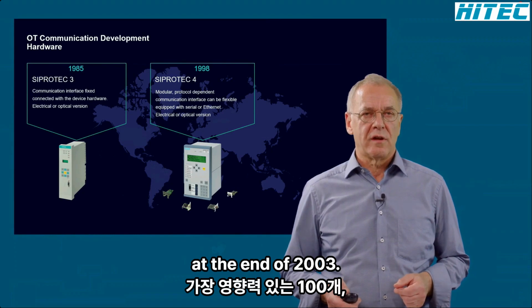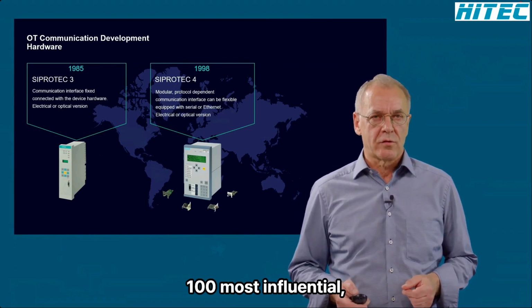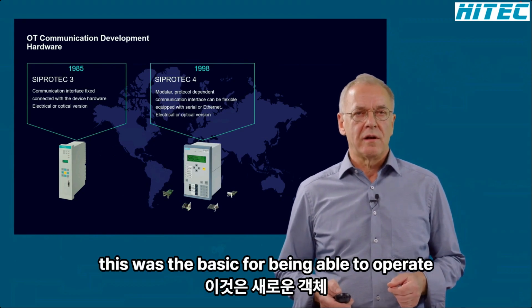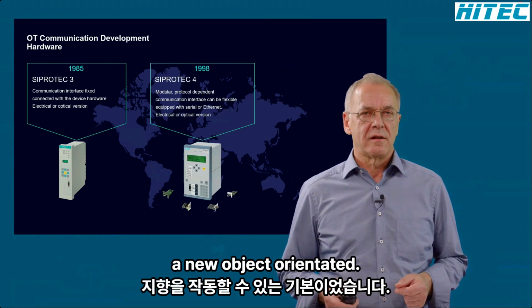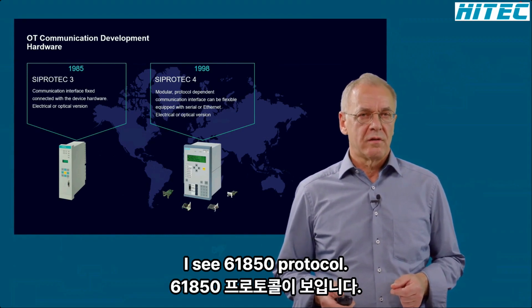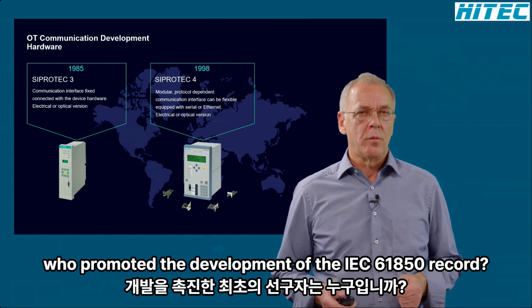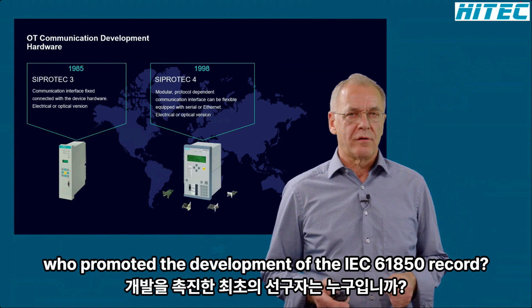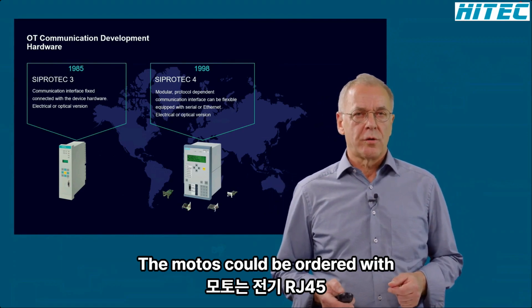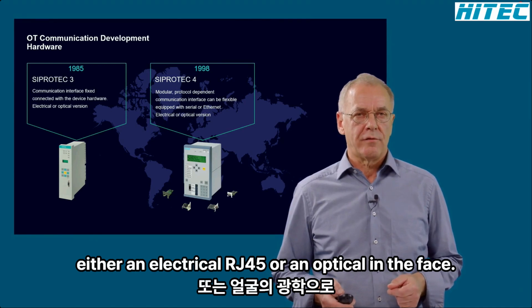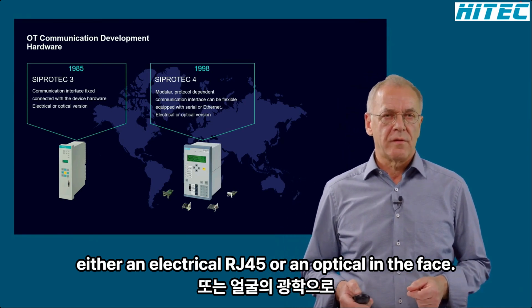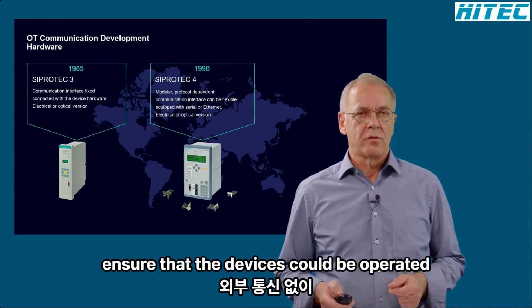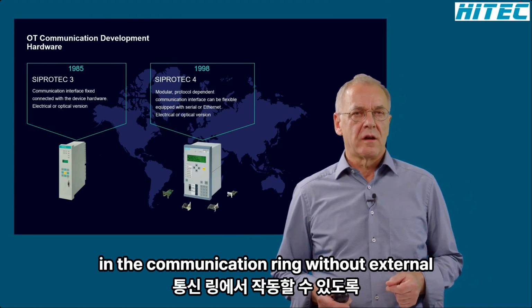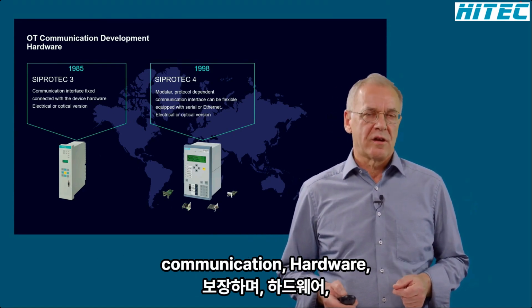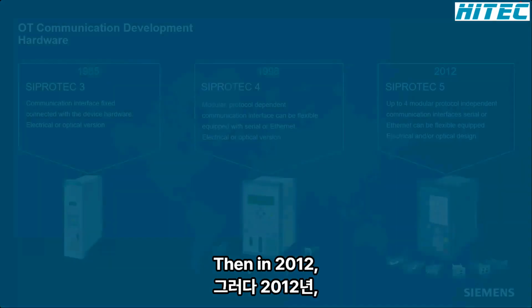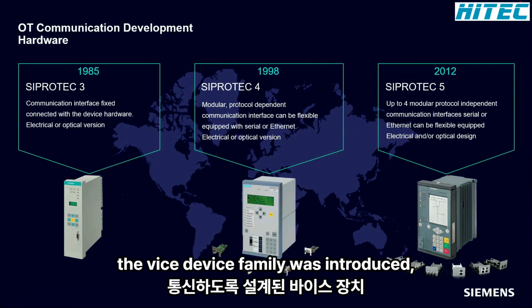At the end of 2003, the Ethernet module EN100 was introduced. This was the basis for being able to operate the new object-oriented IEC 61850 protocol. Siemens was one of the first pioneers who promoted the development of the IEC 61850 protocol. The modules could be ordered with either an electrical RJ45 or an optical interface. The switch function integrated in the modules ensured that the devices could be operated in a communication ring without external communication hardware. Then, in 2012, the SIPROTEC 5 device family was introduced.